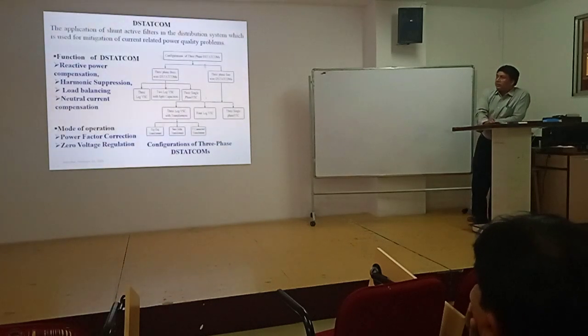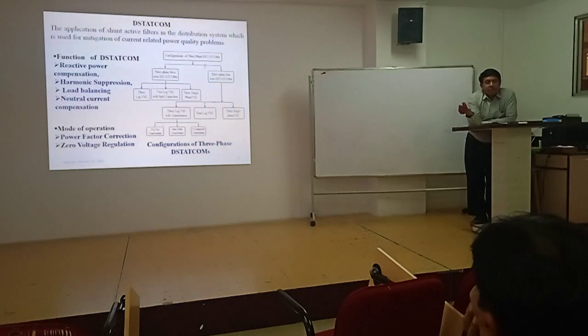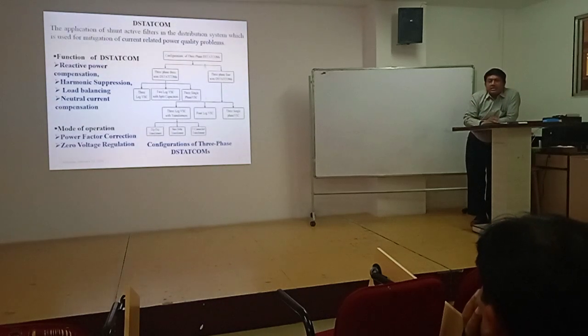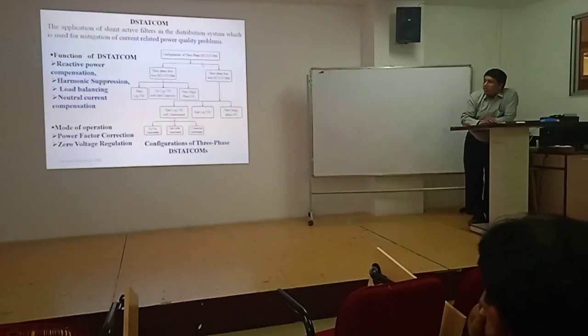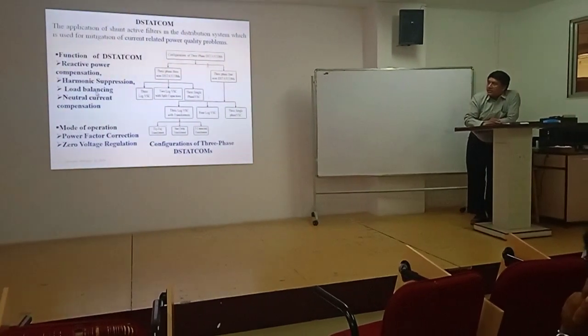Here, if we are going to use this device, in the supply system maybe we have single phase, maybe 3-phase 3-wire, maybe 4-wire. If we have a single phase system, only 2 problems we can solve: reactive power and harmonics, because there are only 2, and balancing is not there. Means by a 2-leg converter we can solve 2 problems. By a 3-leg converter we are going to solve 3 problems: reactive power, harmonics and unbalancing. If we are going to use more legs, 4 legs, we are going to solve 4 problems: 1, 2, 3 and 4.